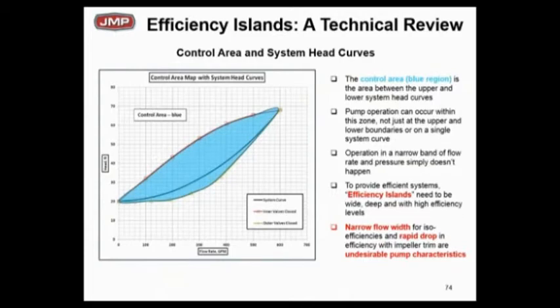Here's the control area, here's the control area from ASHRAE, ASHRAE Handbook calls it a control area. I repeat to you, at a set flow rate, you don't know what head you need. Again, 300 GPM I would need, what about 25 feet of head or 55 feet of head, depends on where I am. I don't know where I am. I do not know. I've got to be satisfied with those conditions.